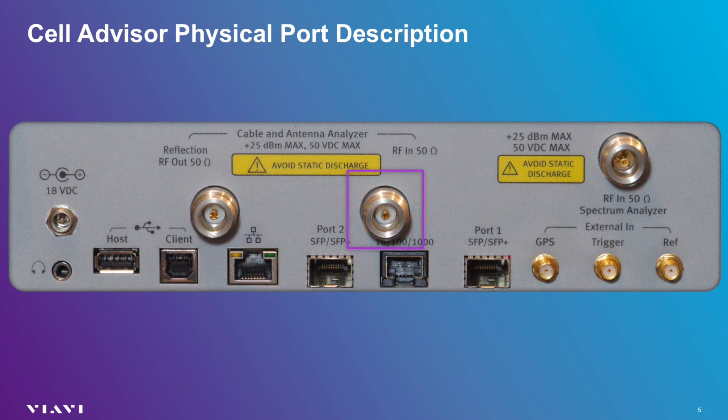When testing devices with extremely high gain, like a bidirectional amplifier with gain exceeding 60 dB, you can use the RF spectrum analyzer port in place of the antenna analyzer input port. Using the antenna analyzer input port to terminate a device under test will allow you to make vector measurements, which include amplitude and phase. If you are using the RF spectrum analyzer port to terminate a two-port measurement, you will only be able to measure amplitude. This is referred to as a scalar measurement.